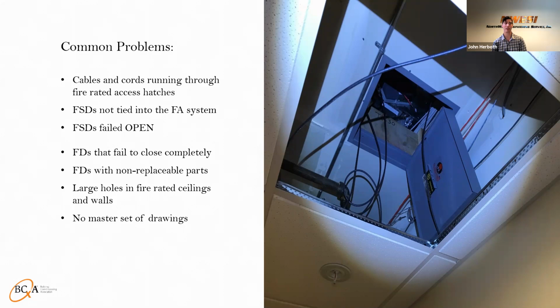If you find a failed open device, you have to start confirming whether or not it's got power or ever depowered, because the motor sometimes doesn't have the spring return, that's just the part that failed. You really have to go in there and use your electrical knowledge to take a look at whether it's the relay that's the problem, the device that's the problem, and then what part of the device.